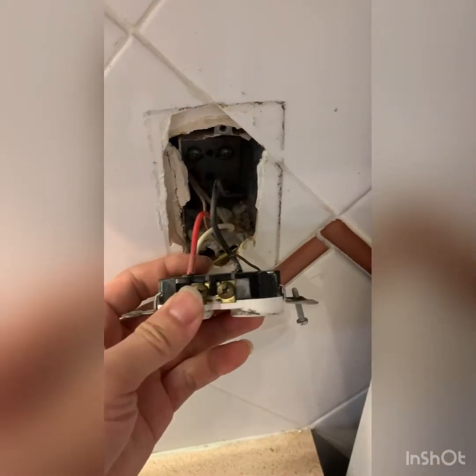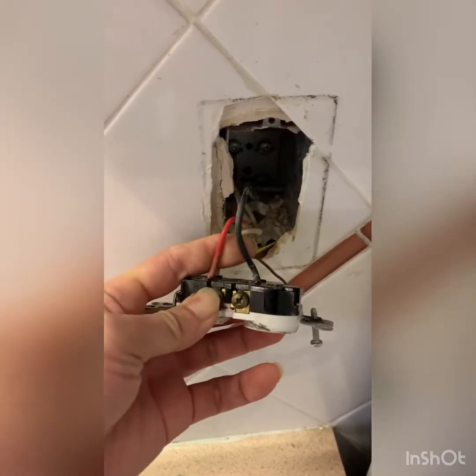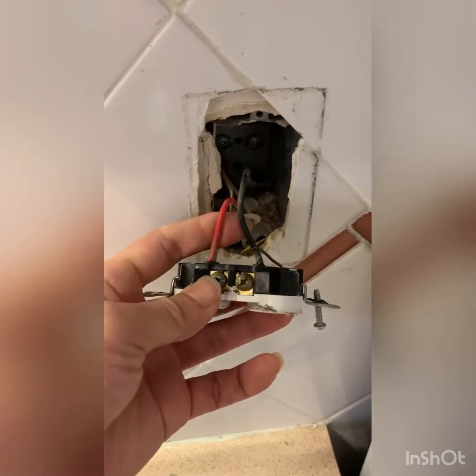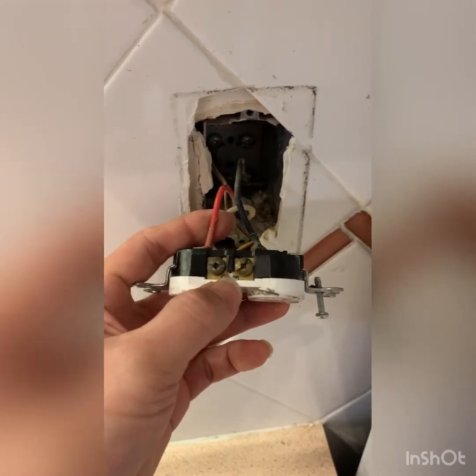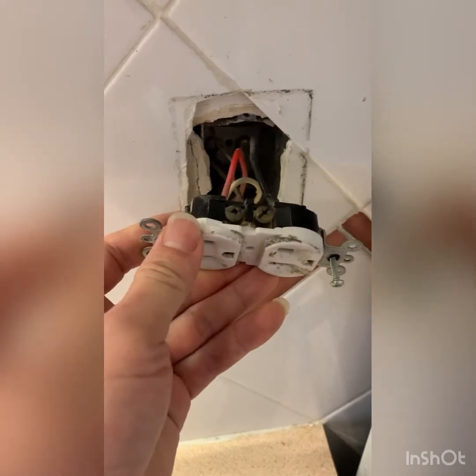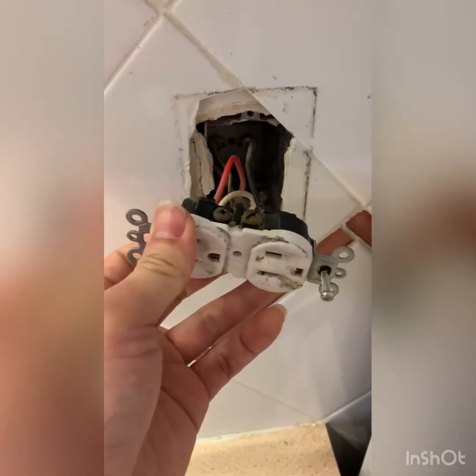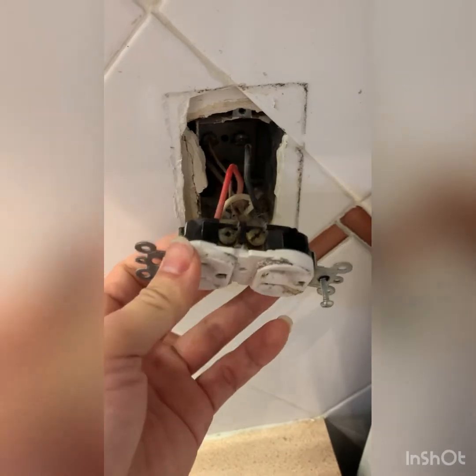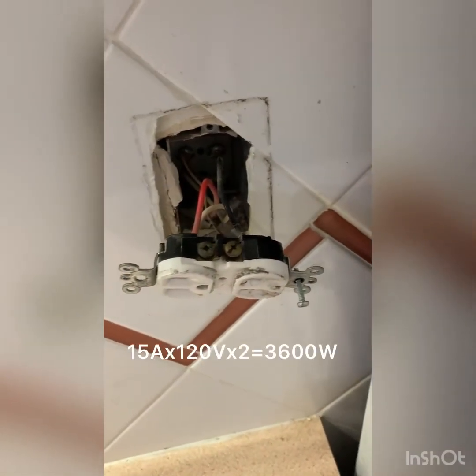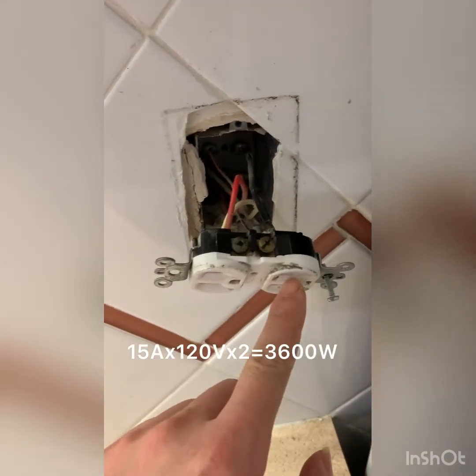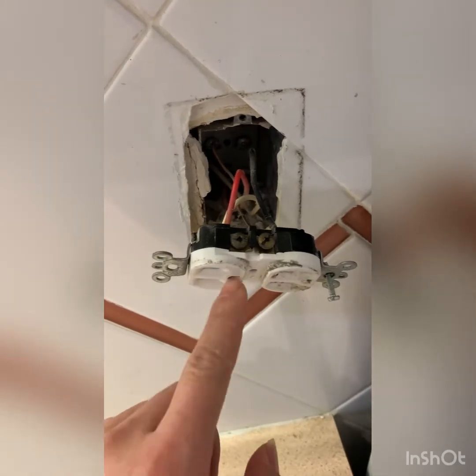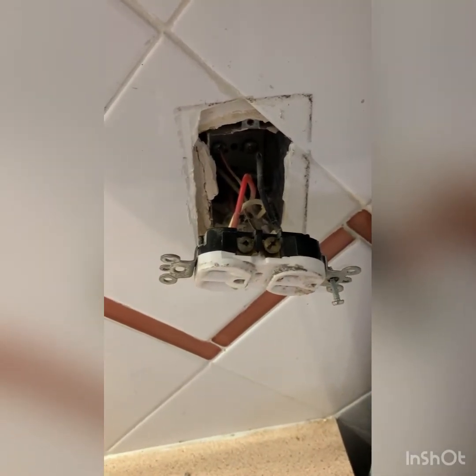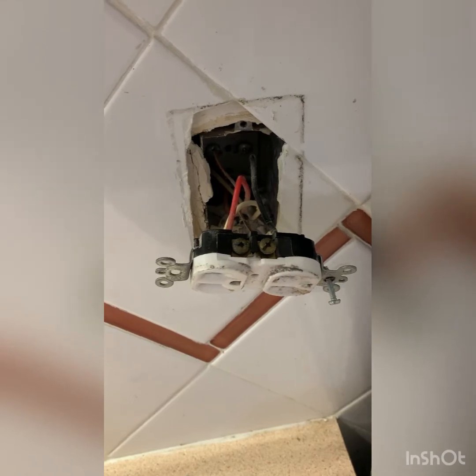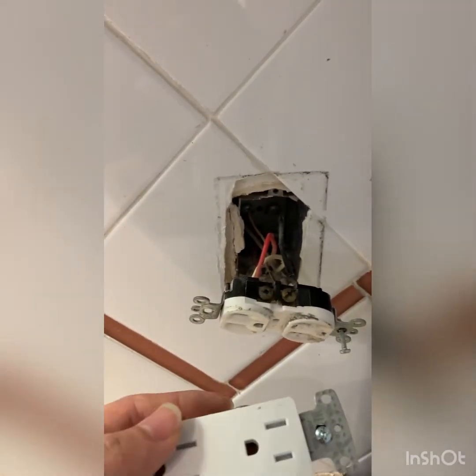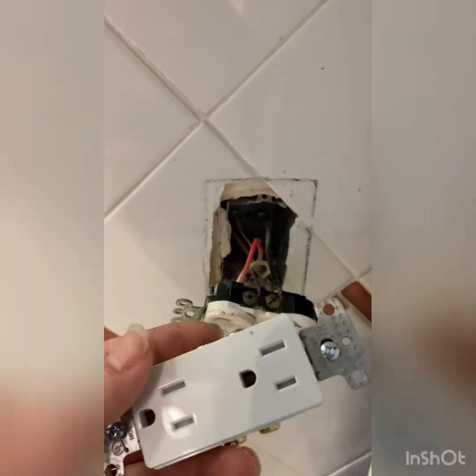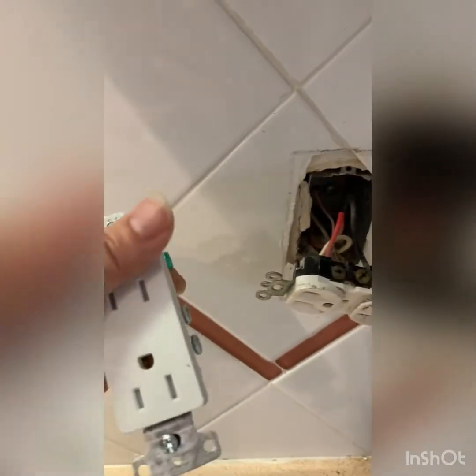By connecting to the shared neutral split circuit, this receptacle's capacity is 3600 watts. Each of the plugs has a capacity of 1800 watts, so it's double the capacity of a normal plug.